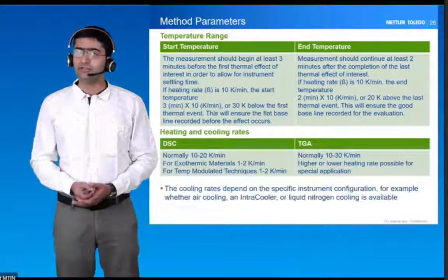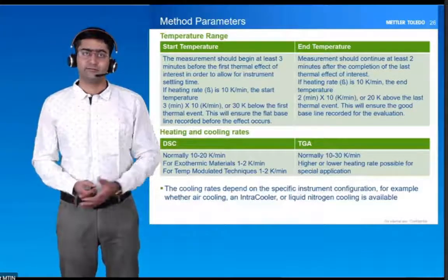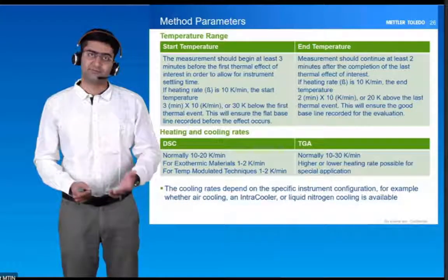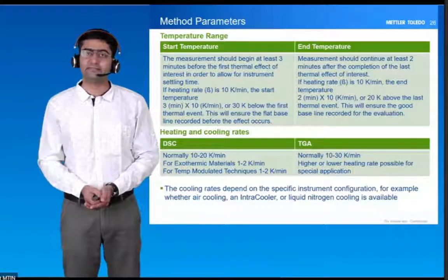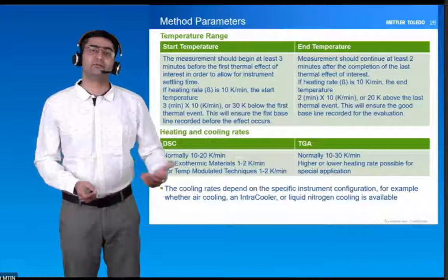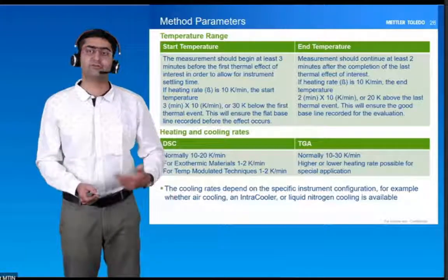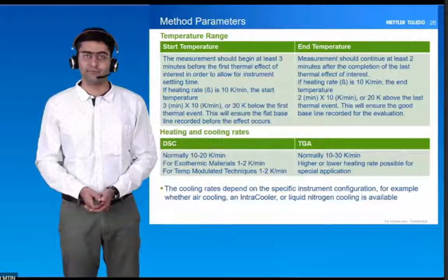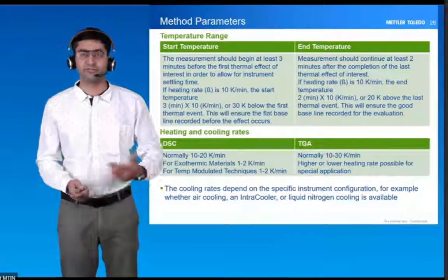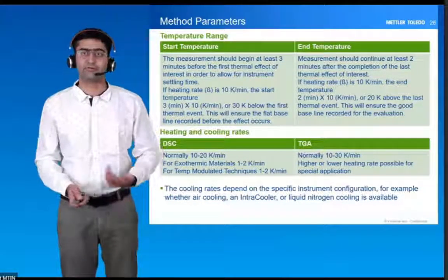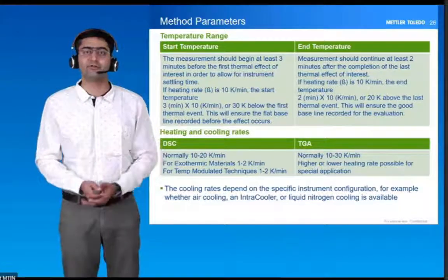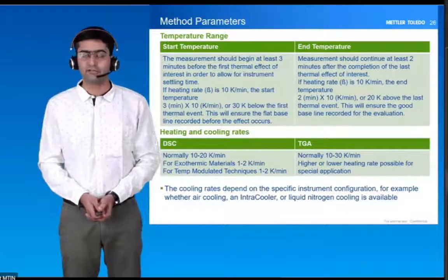The cooling rate, especially in the case of DSC, depends on the cooling system and the configuration you have opted for — whether it is intracooler or liquid nitrogen. Depending on that, you will have different cooling rates possible.